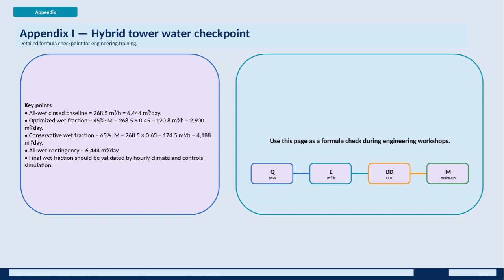It's critical to emphasize that the final wet fraction value should be validated through detailed hourly climate and control simulations to ensure accuracy and system reliability. This page serves as a practical formula check during engineering workshops, helping trainers and engineers maintain precision in their calculations related to water makeup in the hybrid cooling tower system.